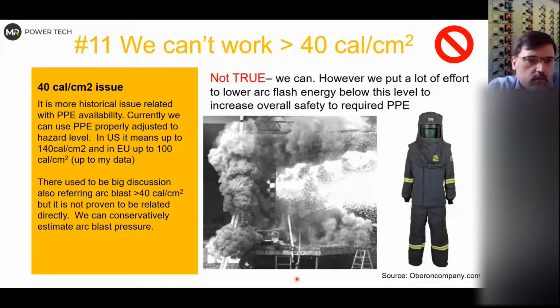So as far as I know, in Europe, we can buy PPE up to 100 calories per square centimeter, and in the US it is up to 140 calories per square centimeter, and purely made, as far as I know, from Oberon company. And there was a discussion behind it that such big energy might release a very big arc blast. And it's kind of half true, because arc blast is not directly related to the energy itself. It's more related to the short circuit current. So we need to have very high short circuit current in a very short time. And the high energy might be just the result of a very long time. It might take 2 or 3, 4 seconds.